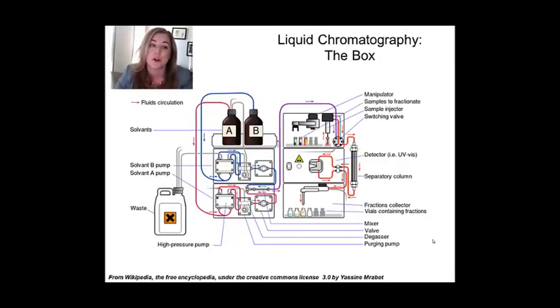Liquid chromatography is actually a more complicated instrument. One of the things it has to do is it has to handle a bunch of solvents, as you see over the left. So now you have solvents getting pushed through the system. And it will often have multiple pumps for that. So the pumping processes and what you need to pump in liquid chromatography is a big deal. And then this column over here to the right is really where all the separation occurs. And so things move differently through the column. And then, of course, you might want to collect what comes off the column. You might be doing it for separation, but that's not really what we'll be talking too much about. But realize, for example, in a lot of pharmaceutical work, you don't just use chromatography to look at what's in a sample. You might use it to purify the sample.